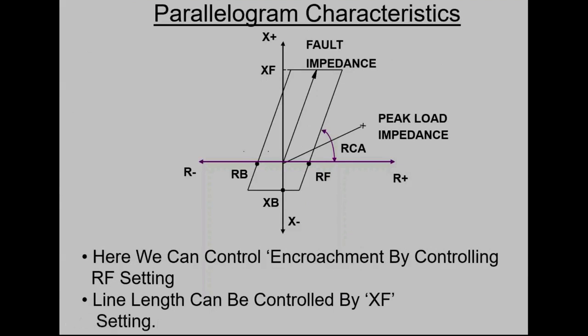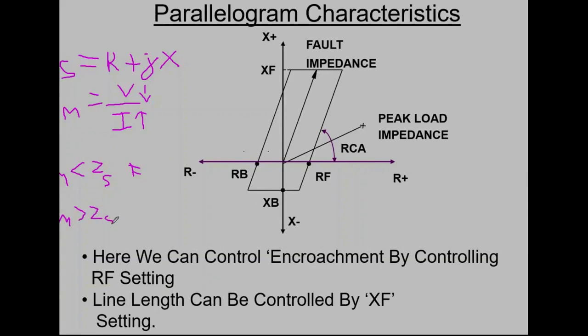Okay, let me write down here. It will be more clearer. Zs = R + jX, and Zm = V/I. When a fault occurs, voltage reduces, current increases. What happens to the impedance? It comes down, because the denominator is bigger than the numerator. So from this we can define: Zm less than Zs is your fault scenario. Zm greater than Zs, the system is said to be healthy.